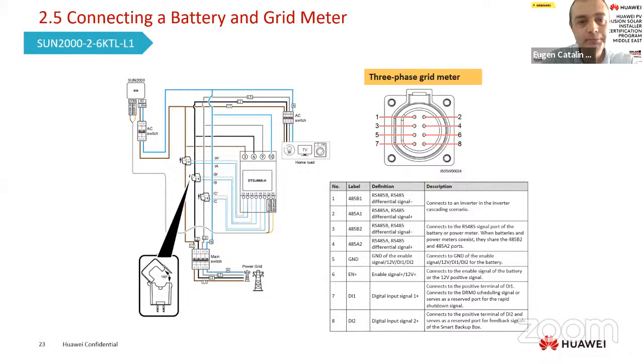Meter installation on the inverter: we will have here L1, for example, a three-phase meter. We know how to install the meter. We need to install the meter at the main point of consumption, to measure all the consumption in that place, not a secondary one. We will not put the CT on the inverter cable. The CT should be installed on the grid cable. You have there a grid meter and your main switch. So the CT will be installed on that cable to measure the total power in that place. After we install the meter correctly, we connect the meter through RS485 communication to the inverter.